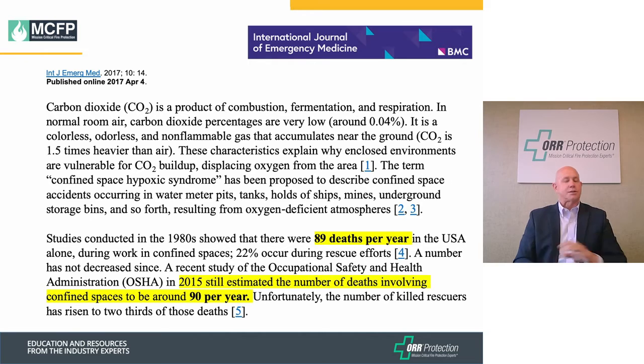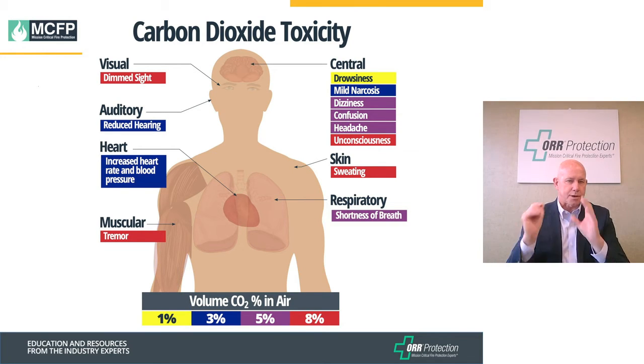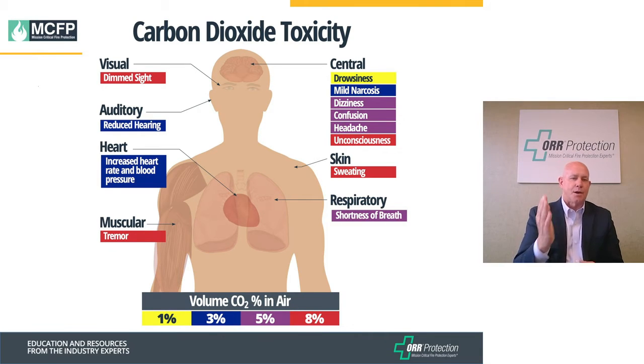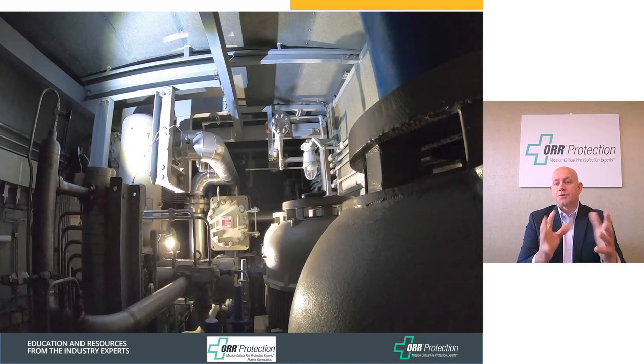CO2 is an awesome firefighting agent with good ability to suppress fire across all three sides of the fire triangle, but we have to be very cautious. We put together a toxicity chart covering 1%, 3%, 5%, 8%, and above. We share this with all of our power generation customers to post on their bulletin boards as a reality reminder — not a scare tactic, but a factual one.